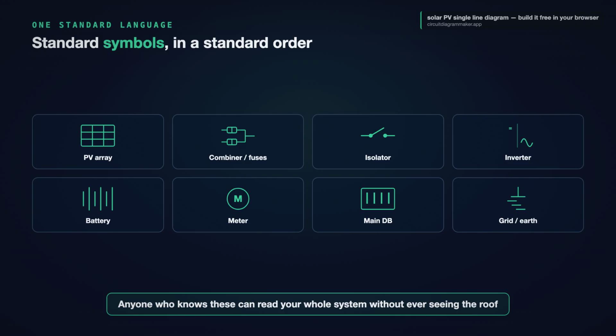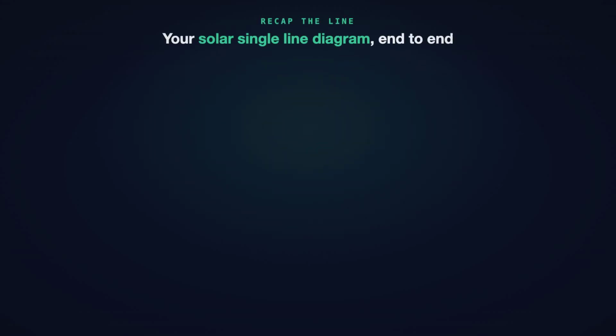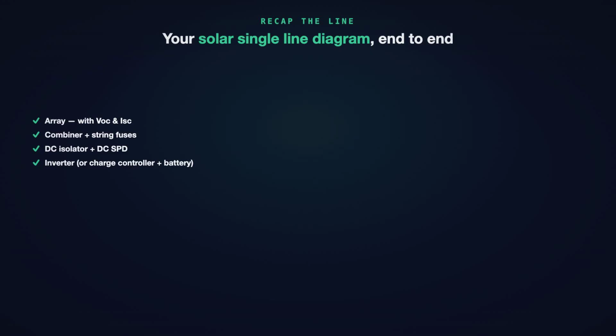Let's recap the line. Array with its Voc and Isc. Combiner and string fuses. DC isolator and a DC surge device. The inverter, or a charge controller and battery for off-grid. The battery with its own fuse. AC isolator, AC breaker, AC surge device. Meter, distribution board, grid. And earth, bonding all of it together.